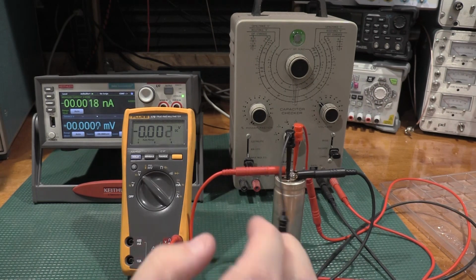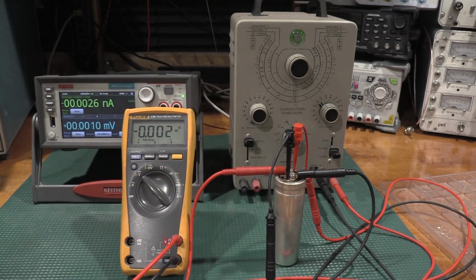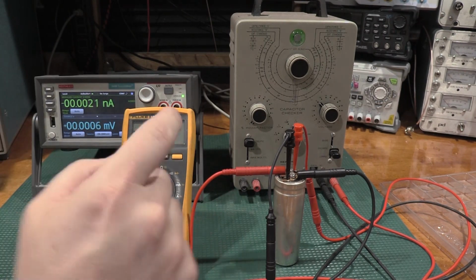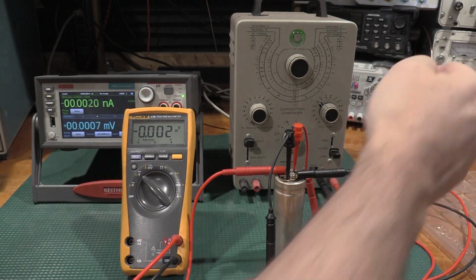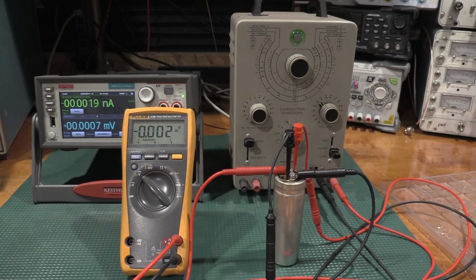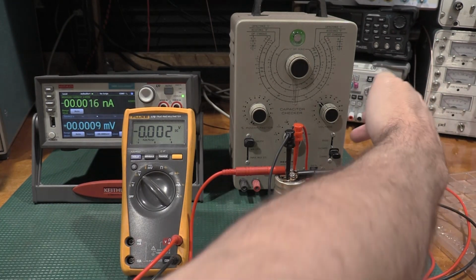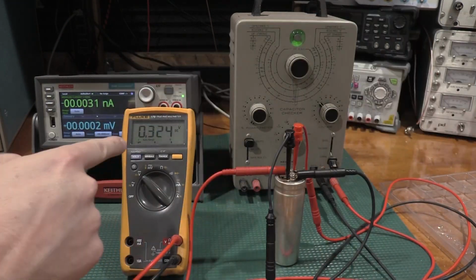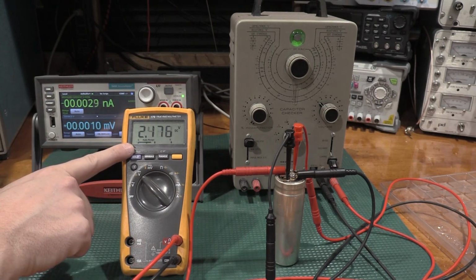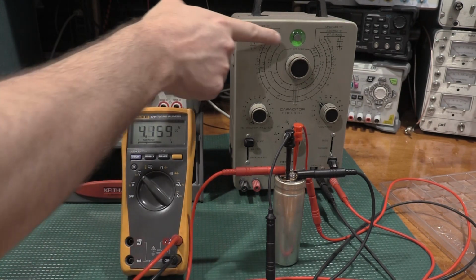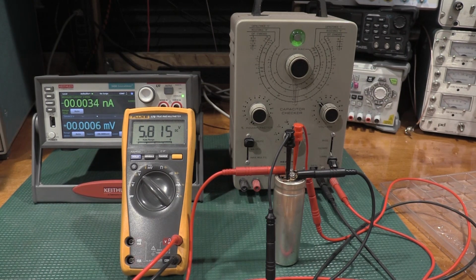Okay, so I have the capacitor hooked up, checking polarity, and we'll turn it to the electrolytic because this is an electrolytic. But what we're going to see is I have it on the 50 volts, 75 volt cap, and we'll set it to leakage and watch the meter. See how slow it's charging? So now we'll notice the eye's closed. So what will happen is this is current limited, so it's going to take it a while to charge. This is also a very large cap to be testing on this unit, so this may even not test.